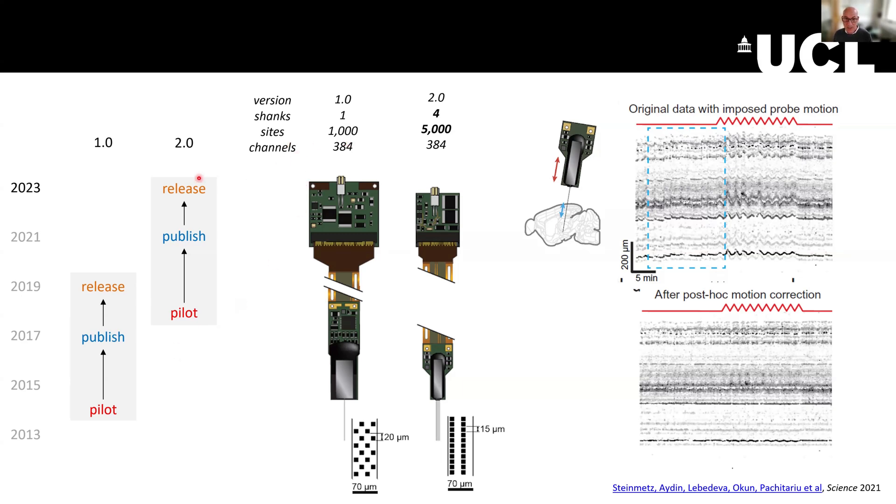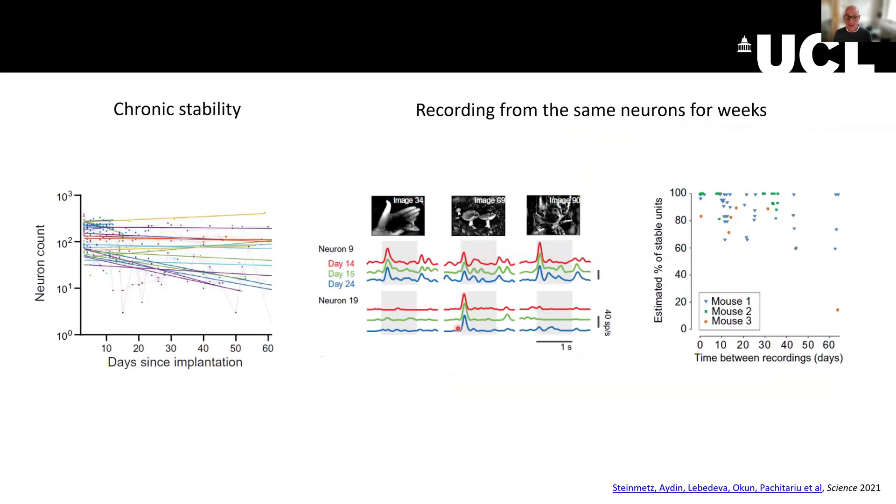These are the two main kinds of probes: the 1.0s and the 2.0s. The thing that really changed with the 2.0s is having more sites, but mostly having four shanks — which means you can now have four shanks with 5,000 sites at the same time in the brain. Also, the arrangement of the sites became linear, which allowed for motion correction, which was very useful.